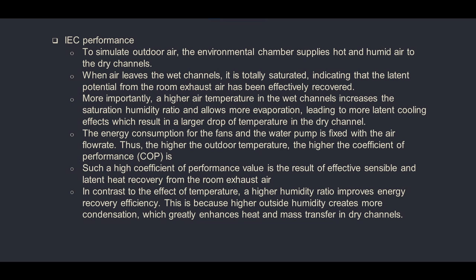IEC performance. To simulate outdoor air, the environmental chamber supplies hot and humid air to the dry channels. When air leaves the wet channels, it is totally saturated, indicating that the latent potential from the room exhaust air has been effectively recovered. More importantly, a higher air temperature in the wet channels increases the saturation humidity ratio and allows more evaporation, leading to more latent cooling effects which result in a larger drop of temperature in the dry channel.